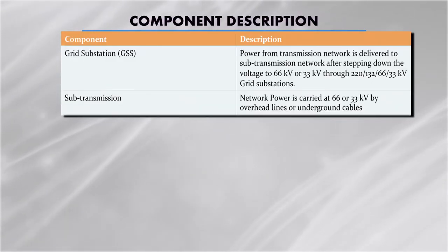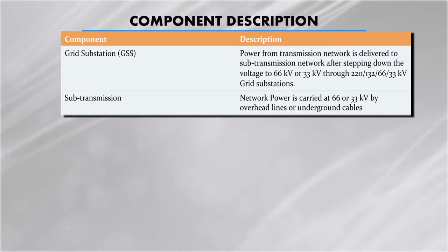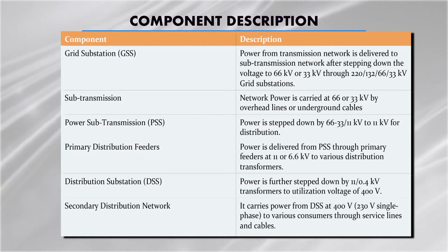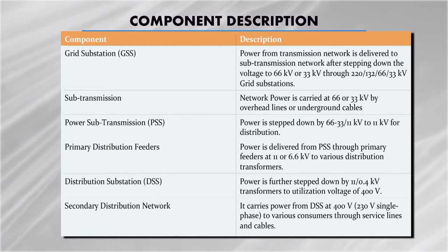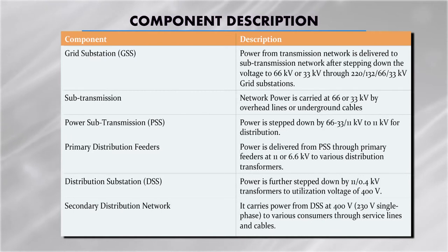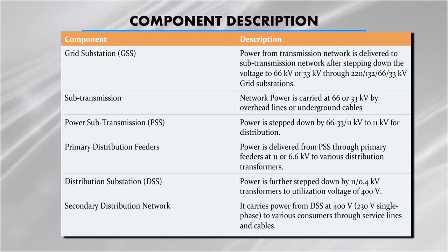In the sub-transmission system, network power is carried at 66 to 33 kV by overhead lines and underground cables. At the distribution substation, power is further stepped down by 11 kV / 0.4 kV transformers. A transformer is used either as a step-up or step-down transformer — the voltage can be stepped up or stepped down from one level to another for utilization purposes. The transformer is a very essential piece of equipment for the power transmission and distribution system.